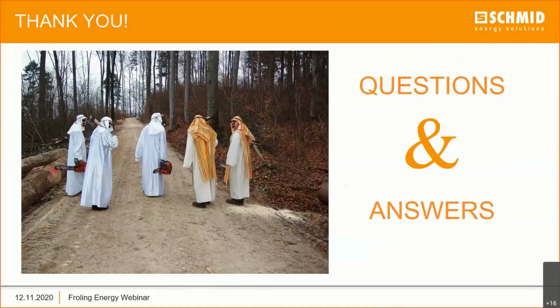And it's a little bit of experimentation. You can only go so far on that, but that's definitely what we found: the fines are the biggest variable that causes trouble. So a screened fuel is a very important fuel in this region.